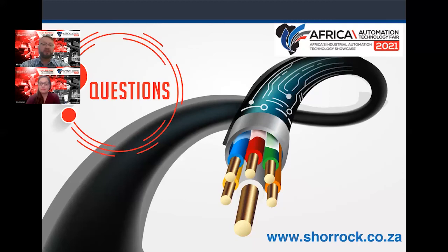Set it up to trip at 32 amps and say that if I reach 32 amps for a period longer than 10 seconds, then I would like to trip. And this would then protect my circuit, because my circuit downline, having a 40 amp power supply, might require less current, and I need to protect it at less current.